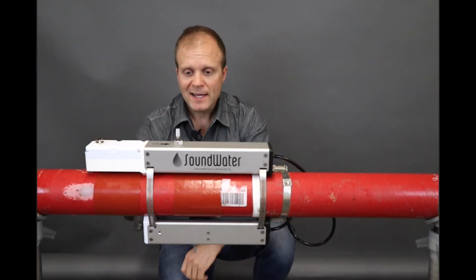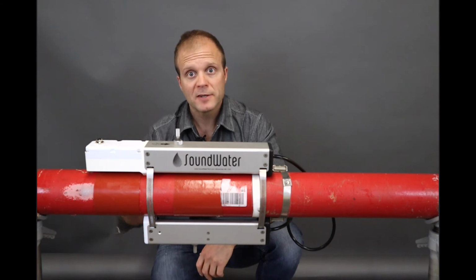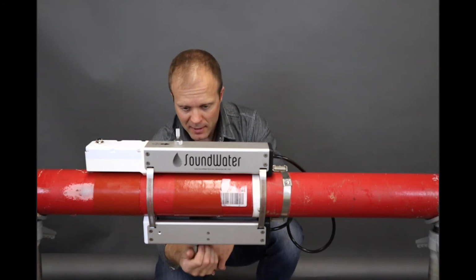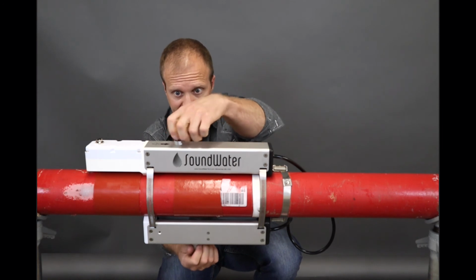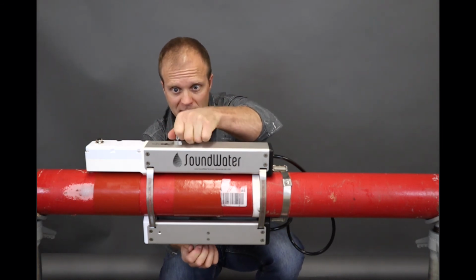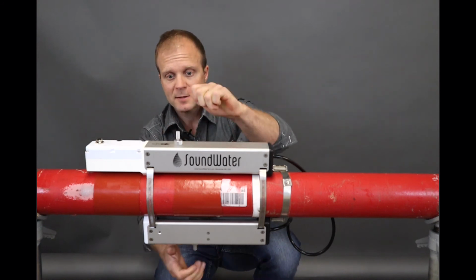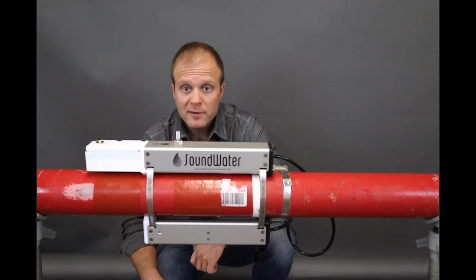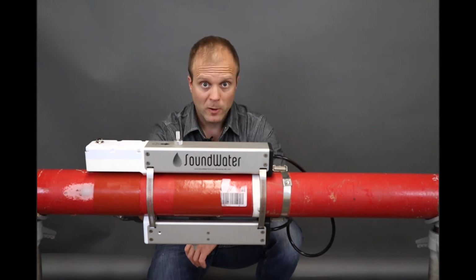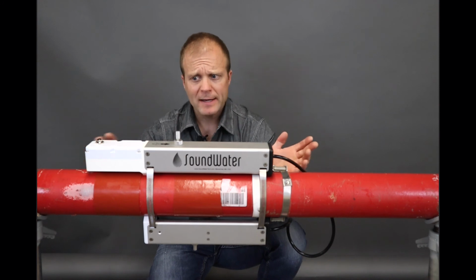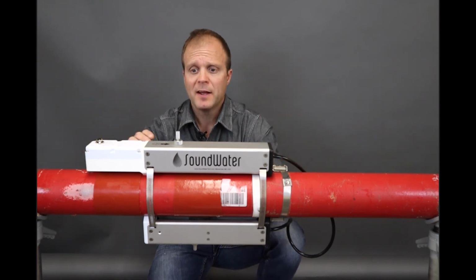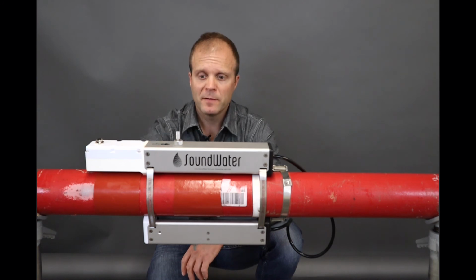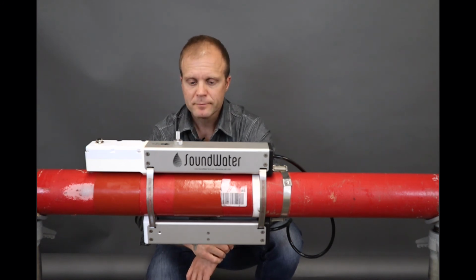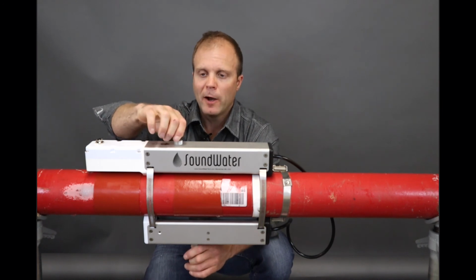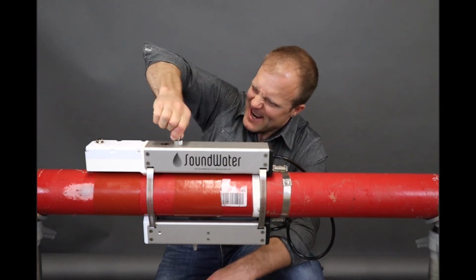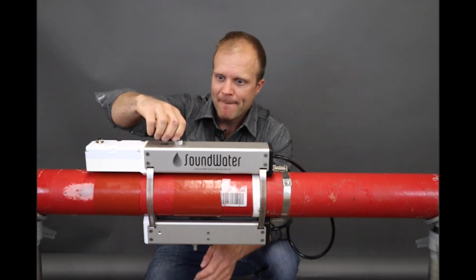Okay, the last step here is to put the transducers actually contacting onto the pipe. So I'm going to move these tall skinny knobs horizontally. I'm turning them clockwise, and they're pressed onto the pipe. And again, cleanliness is important when you first install the meter. After that, it can get dirty, there can be mud, rain, whatever, it's okay. But when you install it, make sure these spaces are clean. That is important. Okay, so again, how tight do we want it? Well, I will turn it down about as hard as I can. Maybe go back and forth.